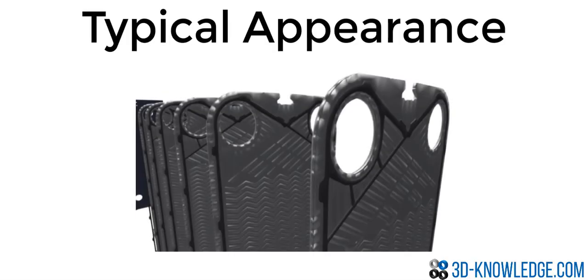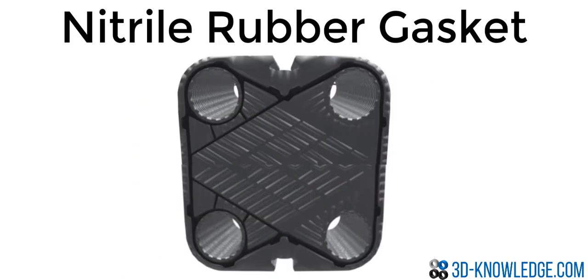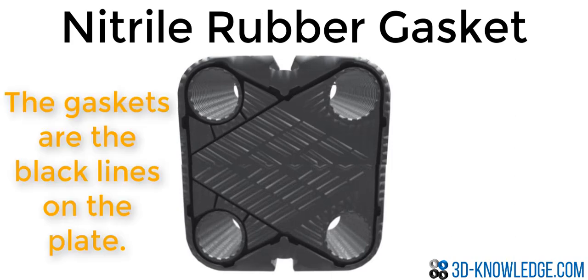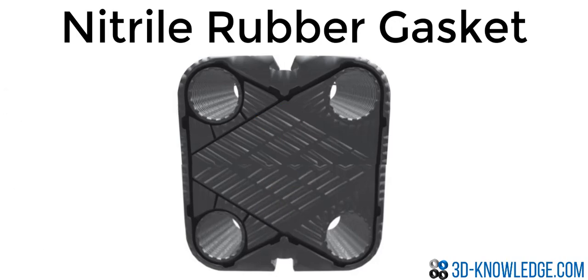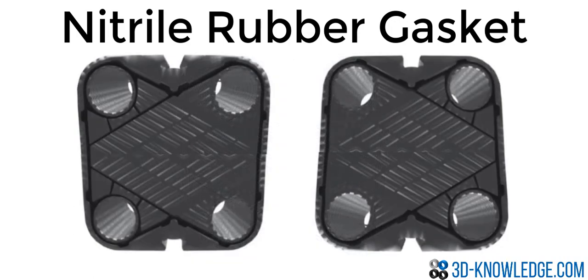Here we can see the appearance of a plate type heat exchanger when all the plates are separated out. One of the most interesting aspects is the nitrile rubber gaskets — these black gaskets that run around the edges of the plate. The reason for their unusual shape is that they direct flow in different directions for each plate. The gaskets look similar, but each plate rotated 180 degrees from the one before it, and this rotation changes the way the fluid moves through the heat exchanger.